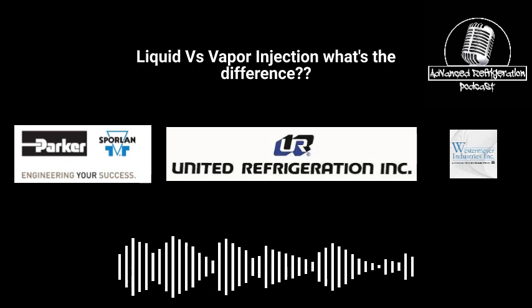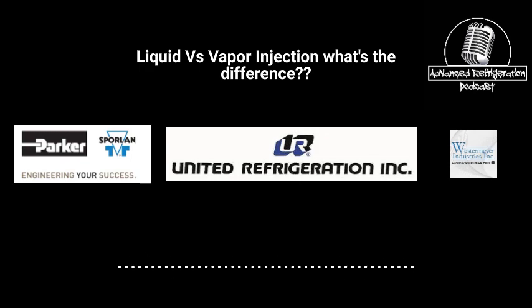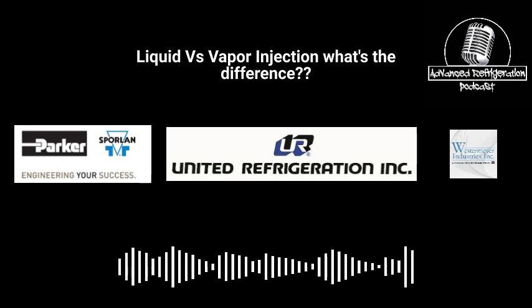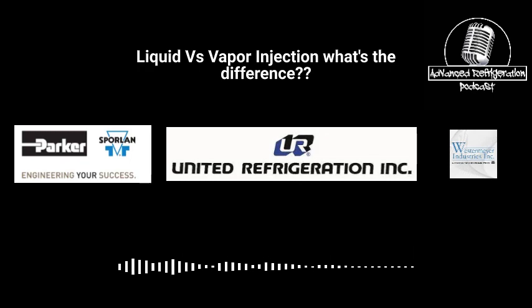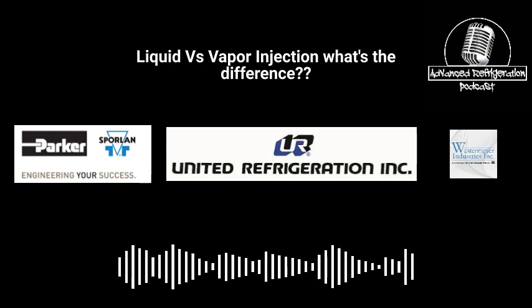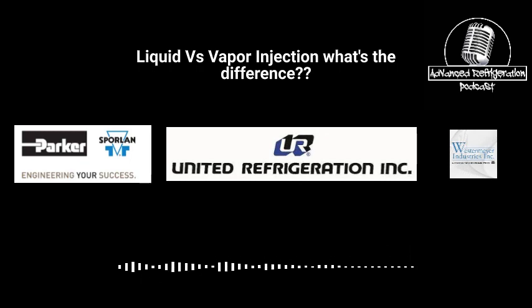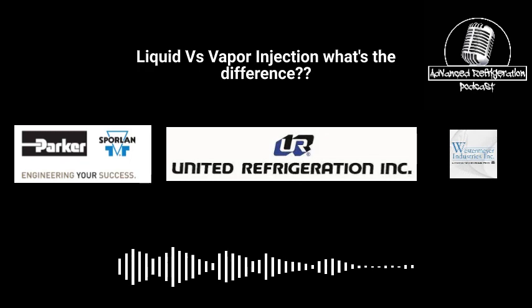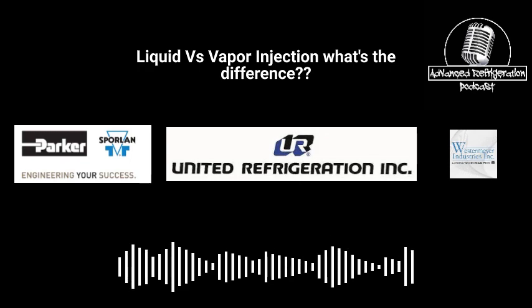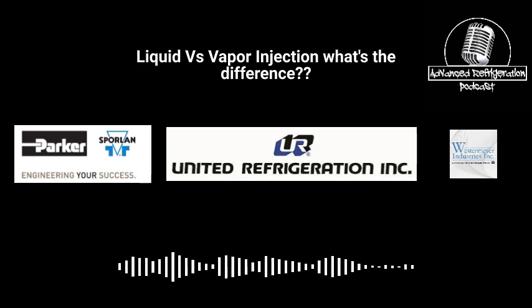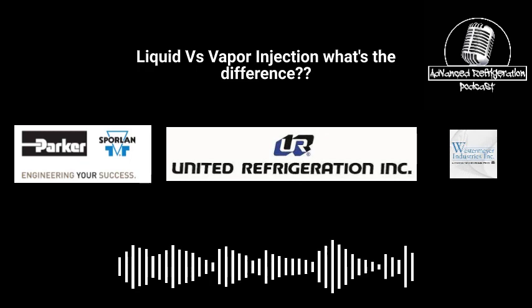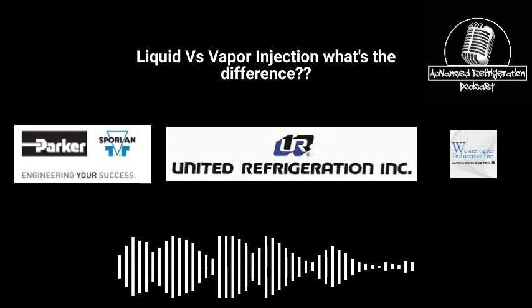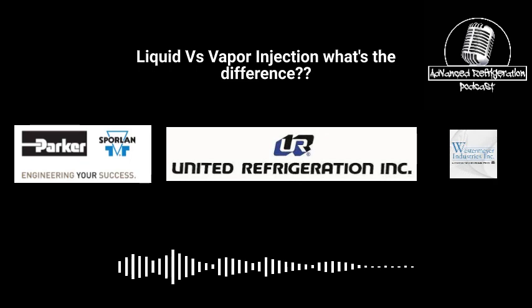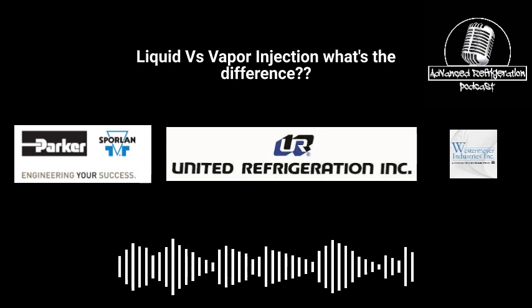With the Y1037 valve, those valves are typically sized off of a couple different factors. You have the horsepower of the compressor, you have the saturated suction that it's supposed to be running at, and then you also have the suction line temperature coming back to the compressor. Based off of those numbers, it'll tell you exactly what valve it wants to have.